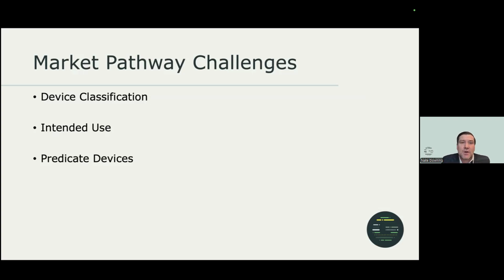The intended use, right? The intended use of an AI/ML device could change based on the data, and it could potentially help patients, but FDA only allows you to market your device for your approved or cleared intended use. And so you have to be flexible in considering what your intended use is. And sometimes I'll tell clients, take a phased approach, go to FDA with your initial, but make sure you understand that you've got some fast follow submissions that might come. Or as we'll see later, and Mark alluded to, there are some change control plan documents we can take advantage of.